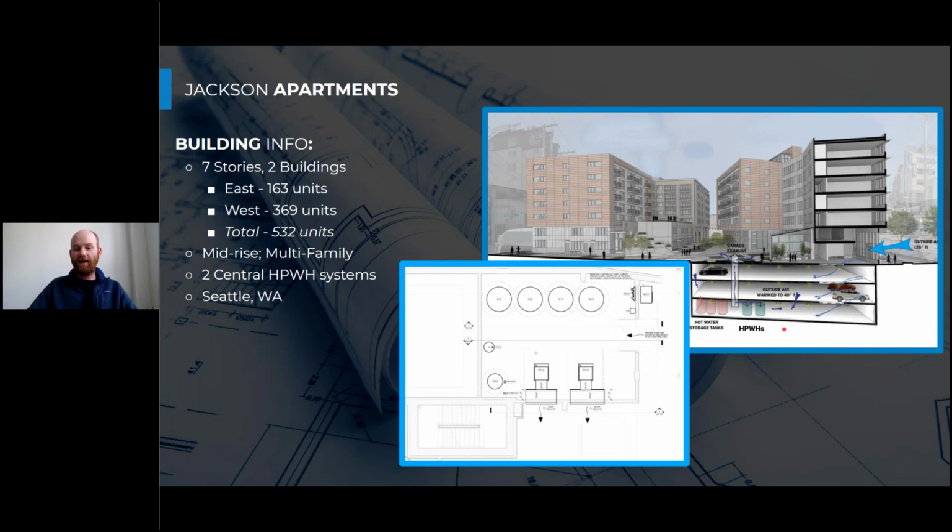So it's a great opportunity to locate those heat pump water heaters in that enclosed parking garage to take advantage of that geothermal energy that we're getting from our ground contact into the garage. And we also do capture some heat from cars. Cars get hot when they run. People are typically driving them into the garage, not pushing them. So those engines are on, creating heat. So when they park, there's a little bit of residual energy we actually get from those cars, which is another pretty neat thing that we weren't really considering early on.